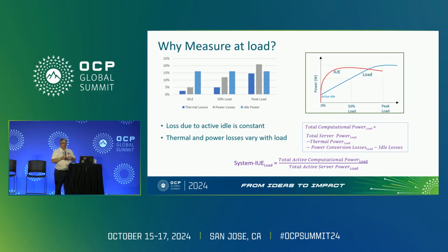Measuring these things at load is part of the definition, determining how you figure out what the idle power is. It's important to measure at various load percentages, because these inefficient uses of power aren't linear and aren't necessarily increasing as load increases. For instance, the power converters, the DC voltage regulators, can be more efficient at higher loads than lower loads, so while total power goes up, the wasted power from inefficient conversion can actually decrease.